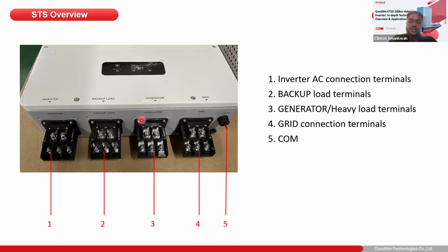And then you also have the diesel generator port. So this is basically a multifunctional or smart port that performs 2 different roles. The first, default role is the connectivity of diesel generators. With this, you can easily connect your diesel generator into the system, and allow your diesel generator to supply power to the backup load, as well as charge the batteries when needed. Aside from diesel generator connectivity, you can also connect a big load to this same port and then establish control.